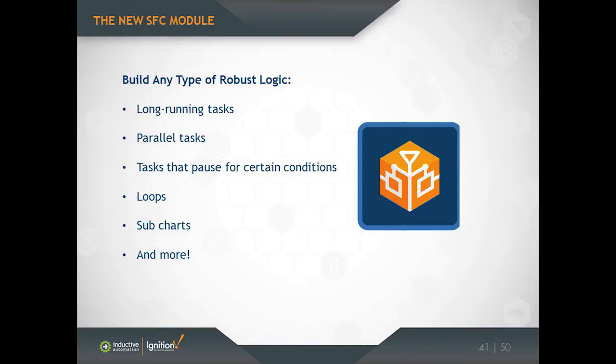So SFCs are very good at certain kinds of things that regular scripts might not be as good at. One of those things is doing very long-running tasks. So you might have an SFC that runs for days, or maybe it just runs indefinitely. It just runs forever. And so we've built our SFC engine in such a way that we expect the SFCs to run for a long time. So long, in fact, that they're built to run even if the gateway is restarted. So if you restart a gateway and you have a chart running, that chart will pause and then resume itself when the gateway comes back up.